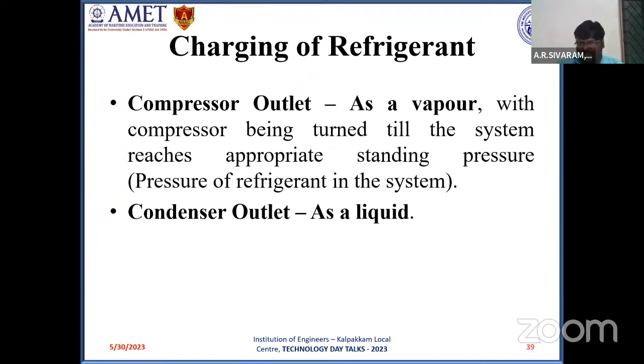Coming to charging, evacuation, and leak detection, I'll just give an outline. Normally, refrigerant can be charged as a vapor at the compressor inlet, not the compressor outlet, and the compressor should be turned on to ensure circulation of refrigerant till the system attains an appropriate standing pressure, that is, the pressure of the refrigerant inside the system reaches the appropriate range. We continue to charge refrigerant at the compressor inlet in vapor state.